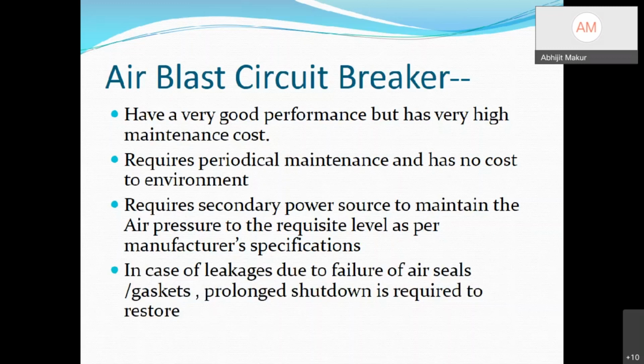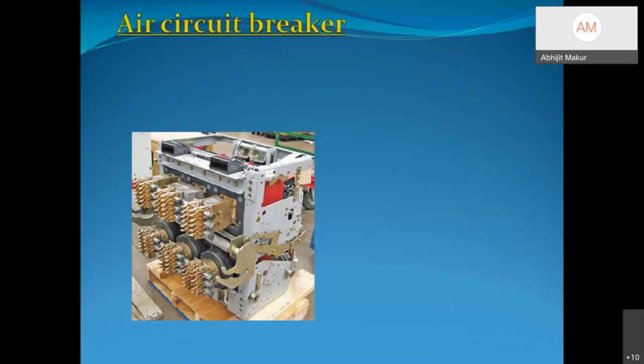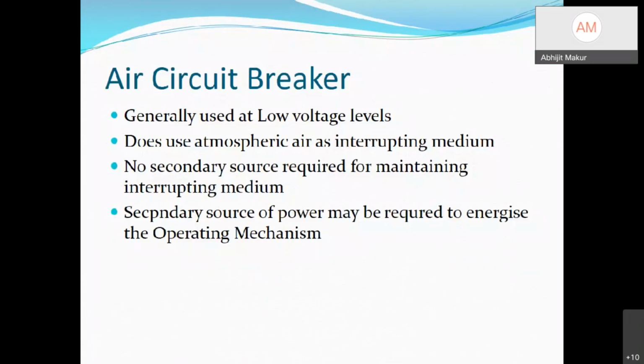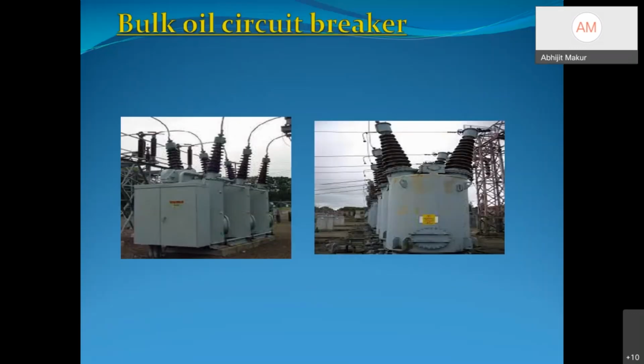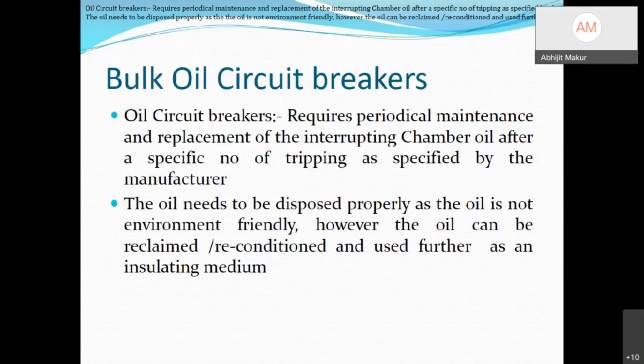The air blast has good performance but a high maintenance cost, because even if there is a problem, you need to take a shutdown and attend to the leakages, and a prolonged shutdown is not available given system conditions. So this has presently become obsolete. Air circuit breakers are used in low voltage switchgear. Bulk oil circuit breakers and minimum oil circuit breakers are in service in old substations, but nowadays they are no more in use. We are phasing them out, and other utilities have also phased them out because of their high maintenance cost and the availability of spares.